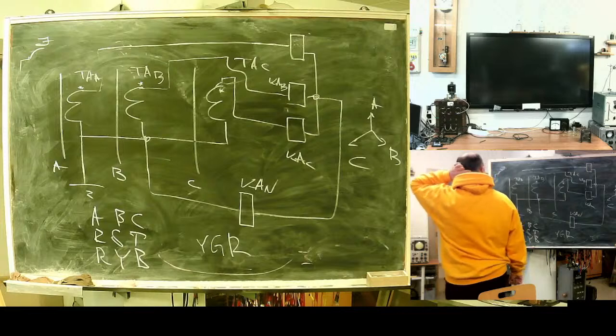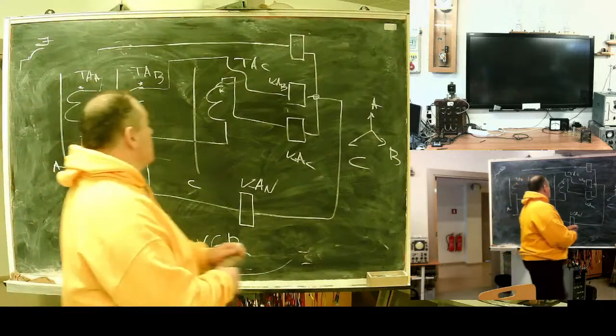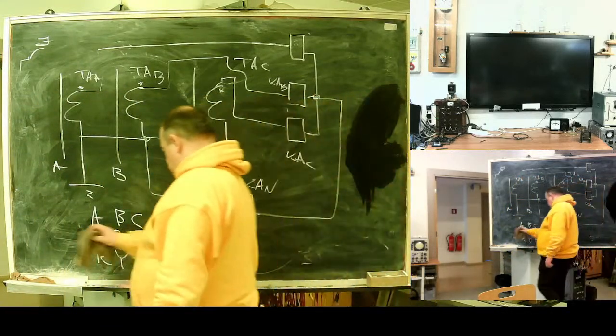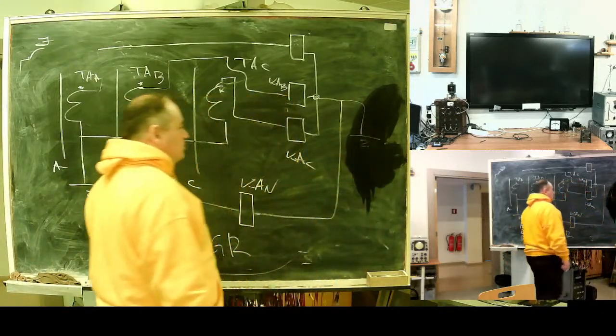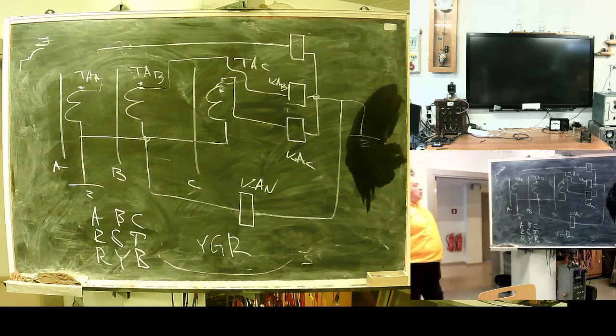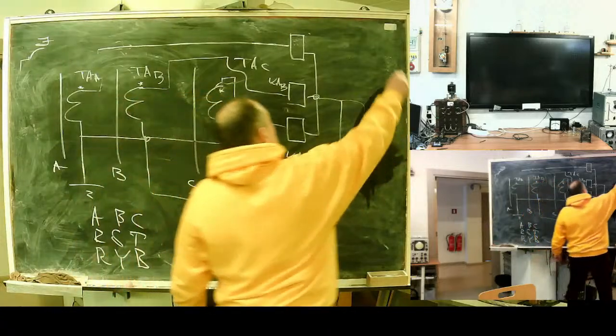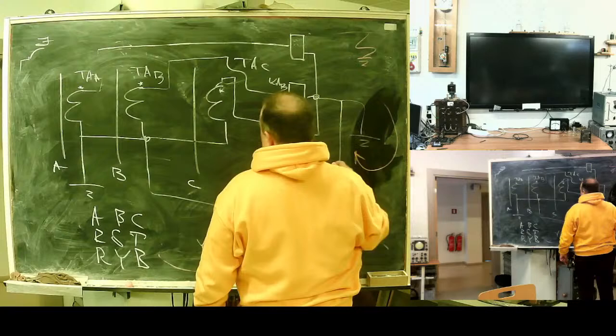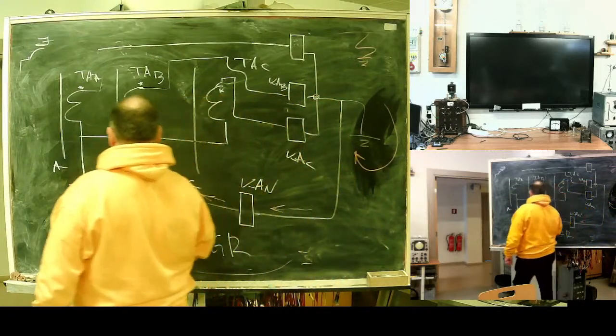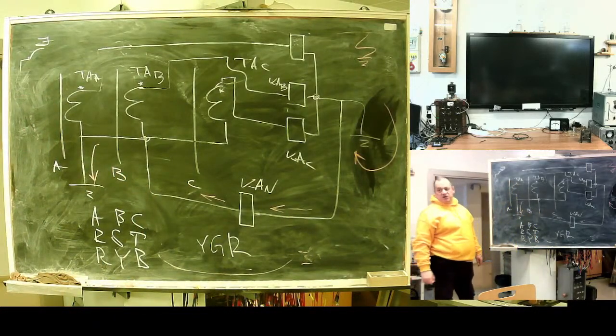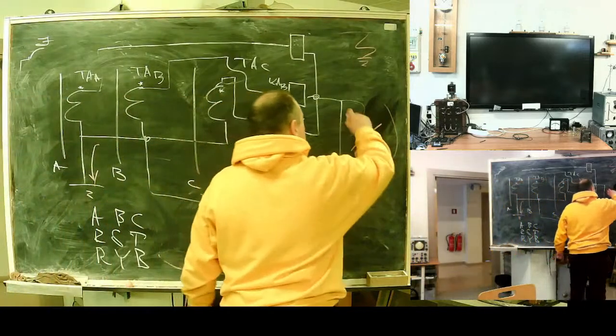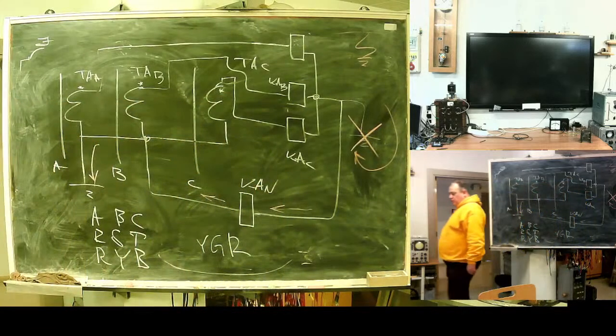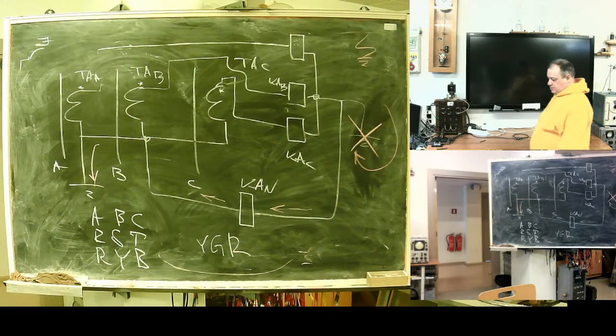Okay, where am I? Yeah, I'm about a mistake. This is a good network, where you can make a terrible mistake. This would be a terrible mistake: put an earth at a star on the opposite side. Why is it a mistake? Because in case of some absolutely foreign fault, the current of this fault will flow through the relay and cause a false trip of protection. Never ever in any case create a double earth. Seriously.